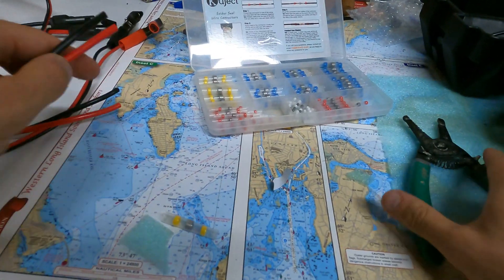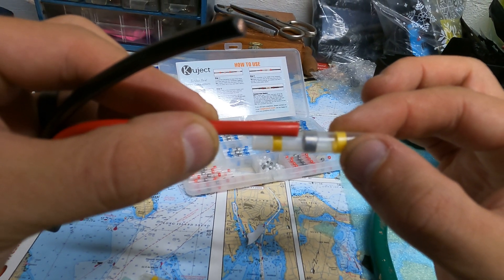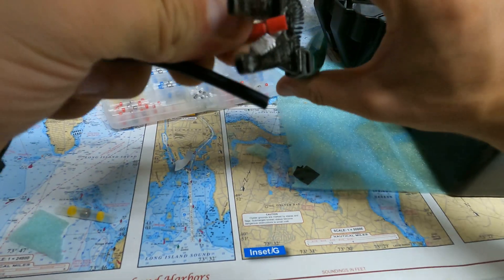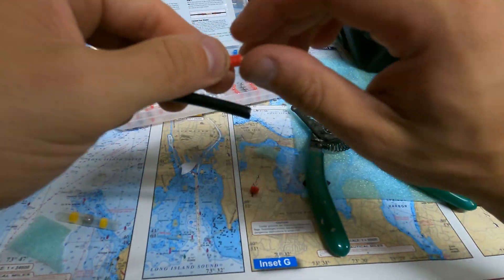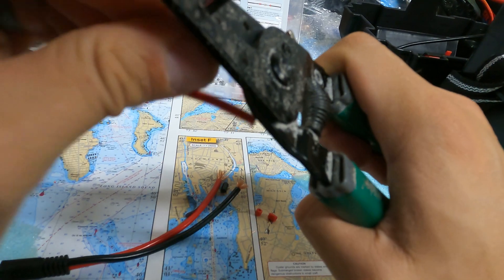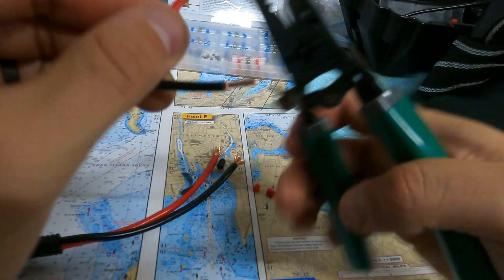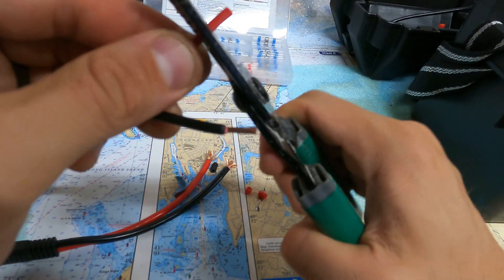I'm just going to strip these — probably a distance about like that, just as much as you want to be inside the sleeve. You're not going to strip this much. This does look like a lighter gauge. The owner's manual said to use, if you're going to splice, 8 or 10 gauge depending on how long. But this is 12, and this is even less. I went with 10, but that's definitely 12. It's fine though, as long as we're a little greater than what's there.